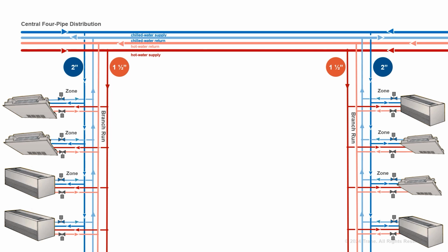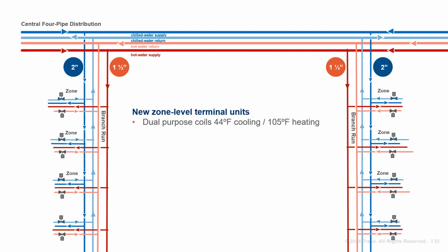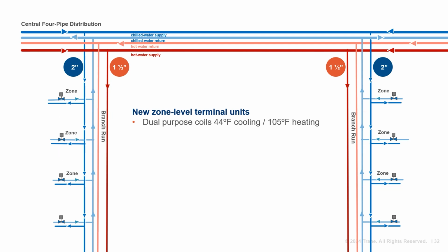Instead of resizing the existing branch hot water piping to match the new flows required, there's already piping that matches the needs. That is the cooling piping. The branch cooling piping can also be used for heating. When replacing the existing units, the new terminal units will be equipped with only one dual-purpose coil that will switch over between cooling and heating. The 1-inch zone chilled water piping is large enough for heating also, so the zone hot water piping and the second heating control valve are no longer necessary.